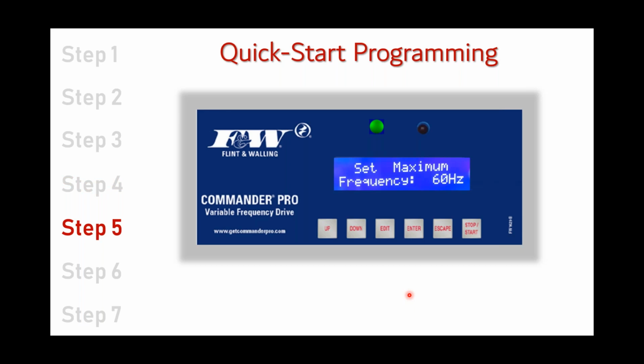Number 4 is the max frequency. And I was trying to explain that earlier on, that the only time we're going to run 80 hertz, the only time, is if it's a submersible pump, A, and B, the motor and the pump end are mismatched. Everything else will run at 60 hertz.